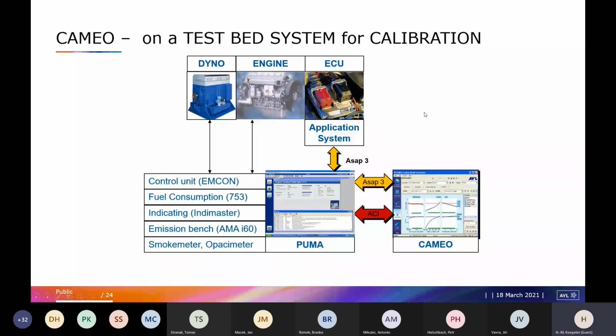But if you want to apply DOE, you should connect CAMEO to such a test system. And again, we make use of standards. We take the ASAP3 standard to get access to the application system, and also for our own test bed, we take a standard. We have internally an even slightly better interface, but in principle it's possible to connect to all test beds supporting this ACI standard - automatic calibration system interface - although this standard is now, I don't know, 18 years old.